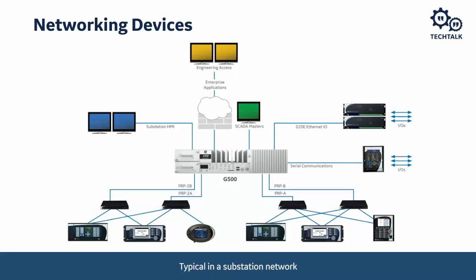In the example shown, the G500 gateway can be used to convert an IEC 61850 protocol used by relays on the LAN level to a DNP protocol used by SCADA or the energy management system on a separate network. A switch is a networking device that connects devices on the network together within the LAN by using packet switching to receive, process, and forward data to the destination device. Unlike less advanced networking hubs, a network switch forwards data only to the devices that are meant to receive it, rather than broadcasting the same data out of all its ports. The exception is broadcast and multicast messages such as GOOSE messaging.